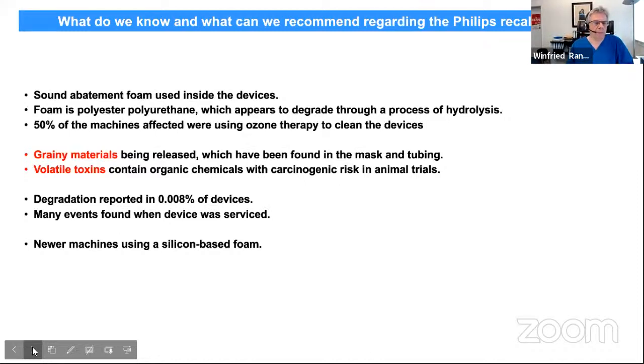What is the problem? The sound abatement foam inside the devices has been shown to degrade through a process of hydrolysis. The foam is made from polyester polyurethane, and it has been found mainly during routine services that there is some degradation leading to grainy materials being released, and they have been found in the mask or in the tubing of the devices.